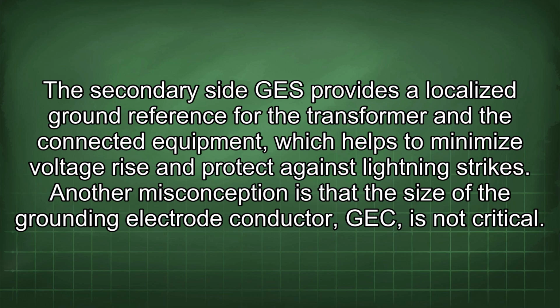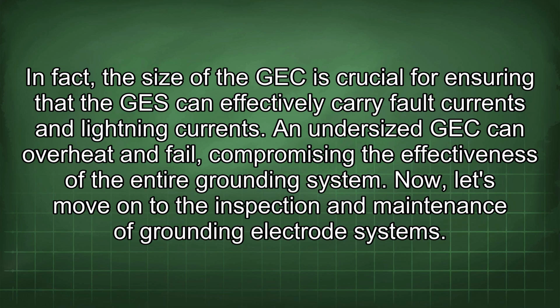Another misconception is that the size of the grounding electrode conductor, GEC, is not critical. In fact, the size of the GEC is crucial for ensuring that the GES can effectively carry fault currents and lightning currents. An undersized GEC can overheat and fail, compromising the effectiveness of the entire grounding system.